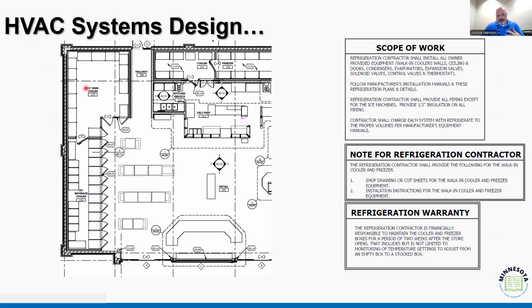And so they're going to have insulation associated with those refrigerated spaces that are not going to be the same as the wall. The exterior wall has its own insulation requirements. We can't say, well, because the beer cooler's there now, we can reduce the insulation for the rest of the building's life. No, because that's not how that works.